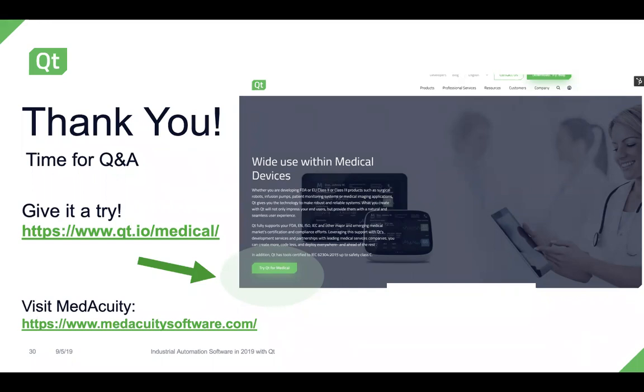The regulatory guidance really isn't mandating a specific methodology. The important thing is to be able to understand and explain to somebody how your requirements led to your design. Traceability is really a tool to do that. But it's more important to understand what your requirements are and how they're implemented by your design.